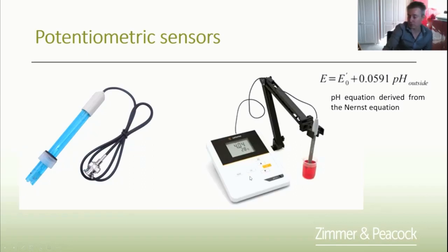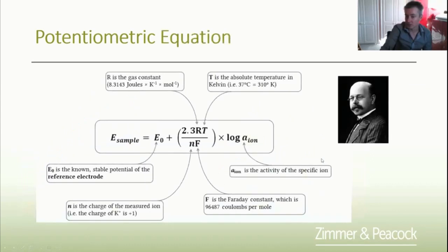So whenever you use a pH meter, it asks you to measure a pH of 4, measure a pH of 10. What it's doing is a 2-point calibration, obviously. Then when you measure your unknown, it's saying, where does that voltage sit relative to those two, the voltage at pH 4 and the voltage at pH 10, and then it's able to calculate what the pH is.